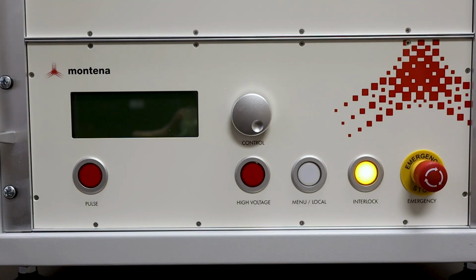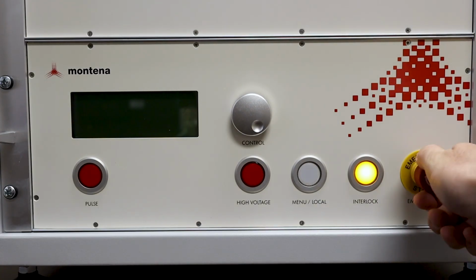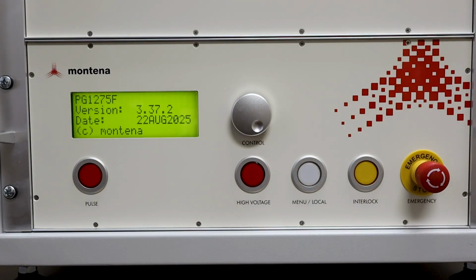So if you receive the unit and the screen is blacked out with the interlock LED lit, even when the interlock is placed in the back, try the emergency button, and to release it just turn it right. And just like that, our system is starting up and we can begin testing.